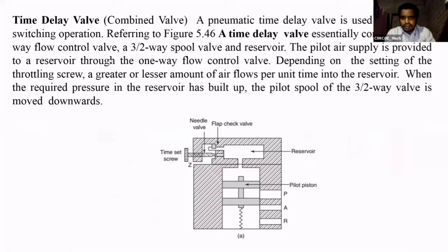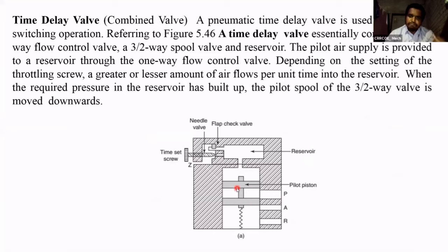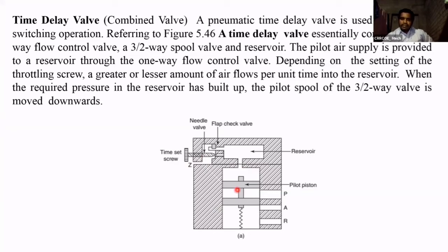Next is the time delay valve. In the time delay valve construction, we have three ports: pressure port, output port, and return port, and we have a spool here — a pilot spool. The closing and opening of the port is done with the help of this spool/slider. Above the spool we have a chamber. We send pilot air — external auxiliary air — that operates the slider. Pilot air is the air which operates the valve. The flow of pilot air is controlled with the help of a set screw.